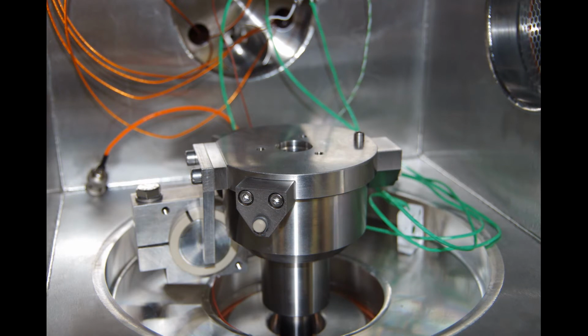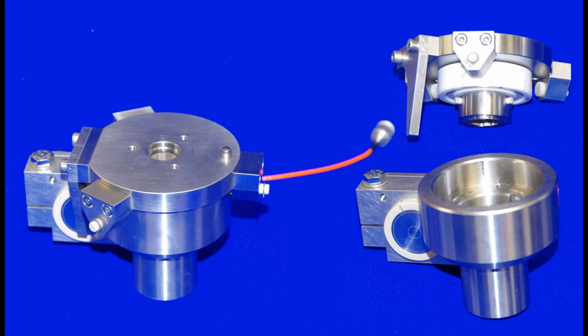At the bottom of the chamber there is a torque reaction mounted hub assembly which carries the lower specimen tooling mounted on top of the loading shaft. This is free to move on the vertical axis. The shaft acts through stainless steel bellows which provide the necessary leak-free sealing. The rotary feed-through and the loading shaft have been carefully aligned during manufacture and no adjustment should be made to the levelling screws. A flexural bearing resists rotation of the hub when torque is applied, and a capacitance sensor measures the displacement, which is proportional to the applied torque.